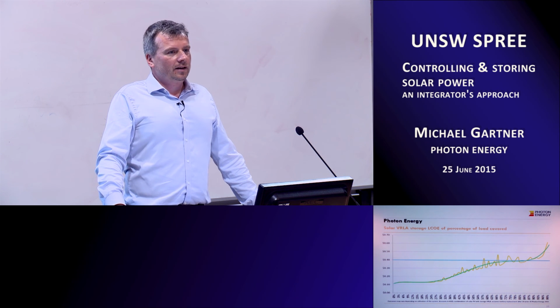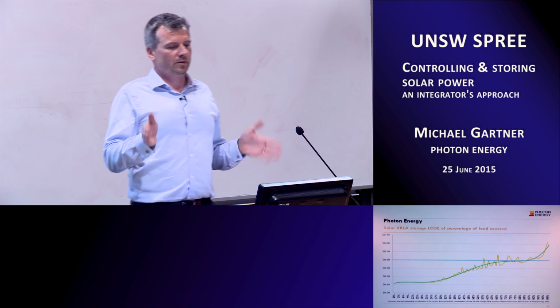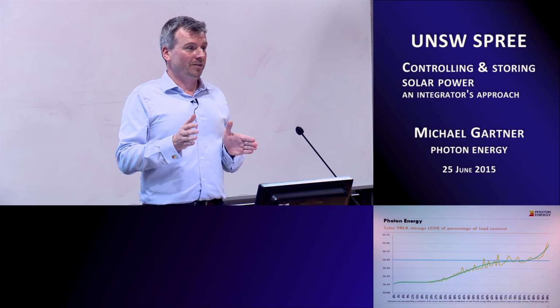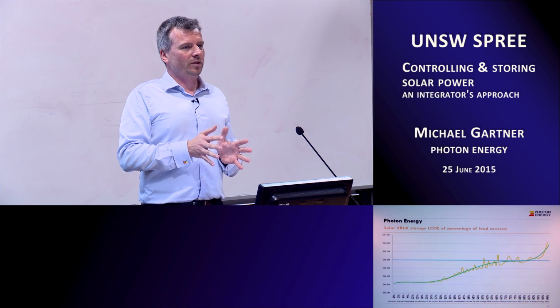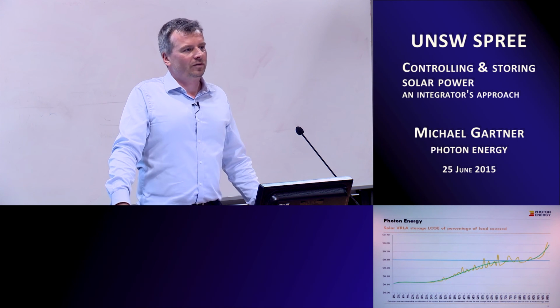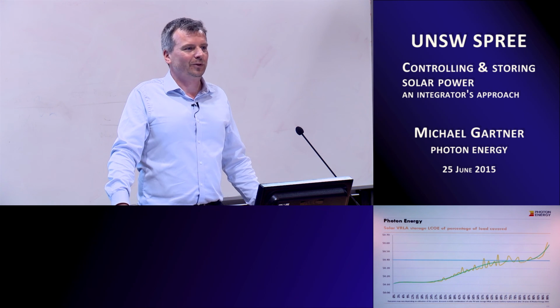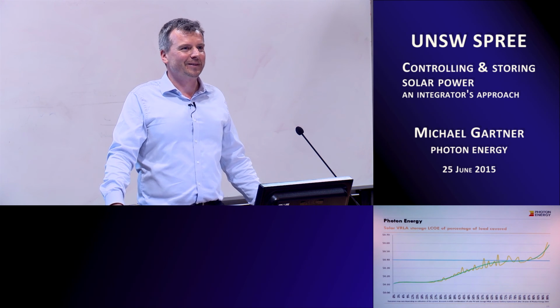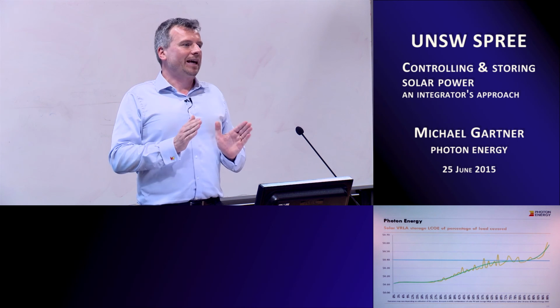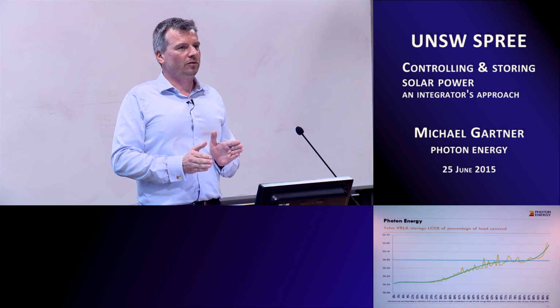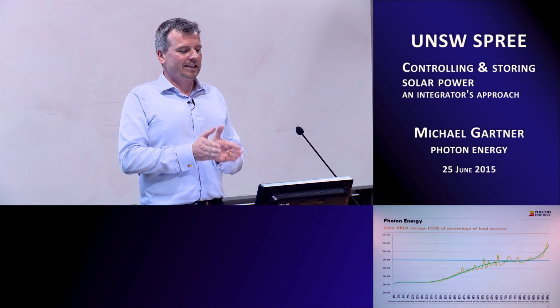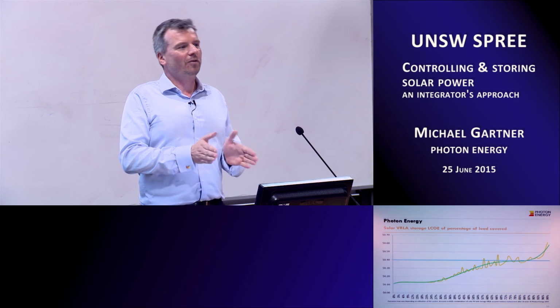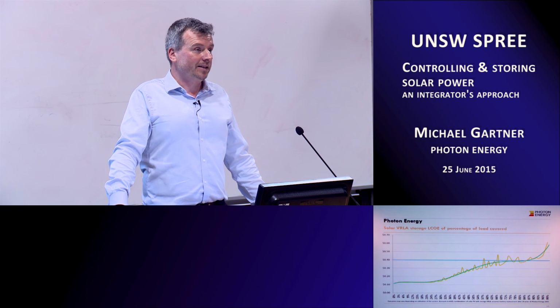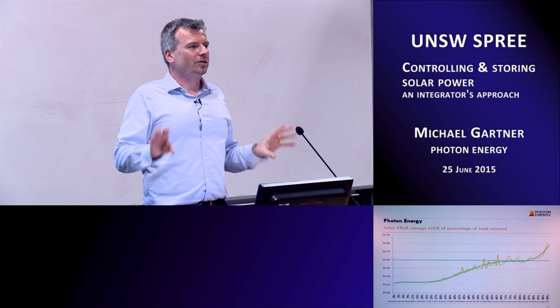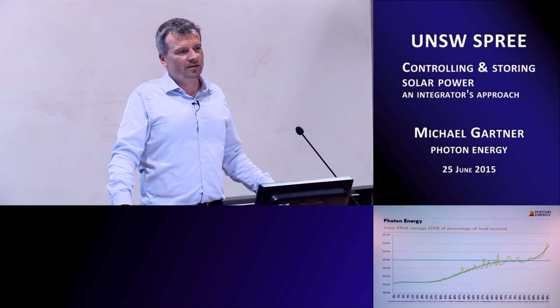As we get bigger, do you think you can reduce cost and enhance overall reliability? Absolutely, yes. Generally, bigger systems are working on quite a large lithium-ion system at the moment, and what's happening there is we've got blocks of batteries, and each of them functions independently. So if one burns or has a failure, we don't want it to ever burn, it has a fire safety system internally, but if something happens, the system continues to operate. That level of redundancy has to be built in. In fact, the customer spec always has a redundancy element, so if we don't meet that, it would be quite problematic. But I think what you're alluding to is right, and these are areas that need to be investigated further.